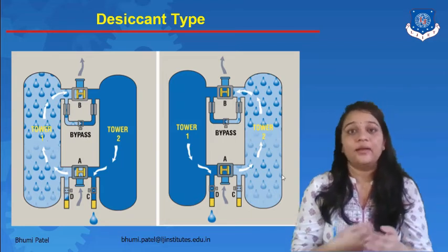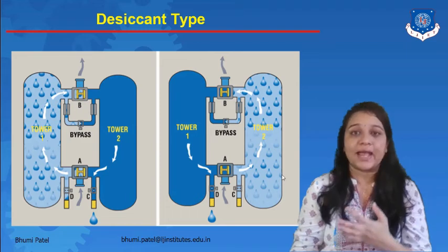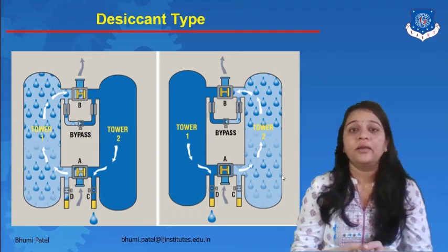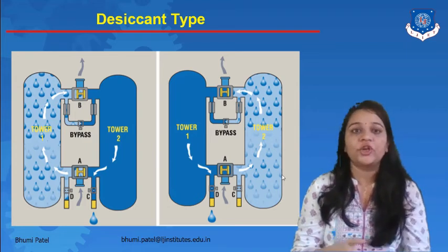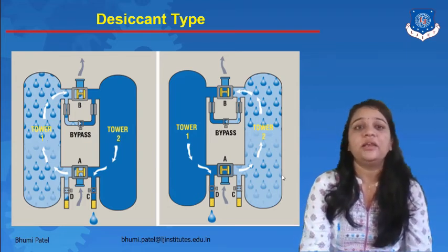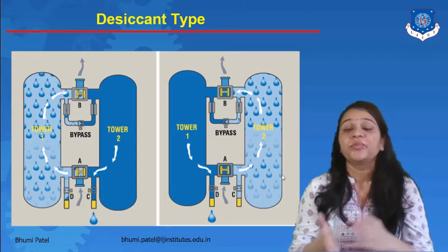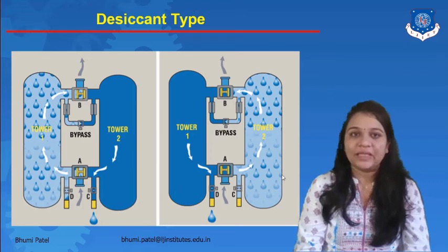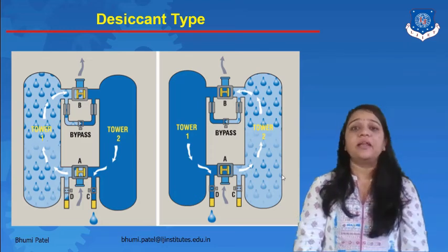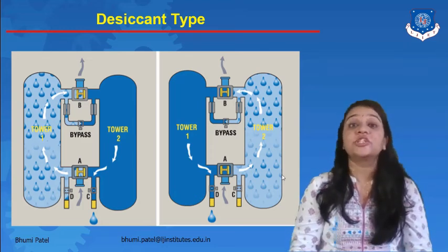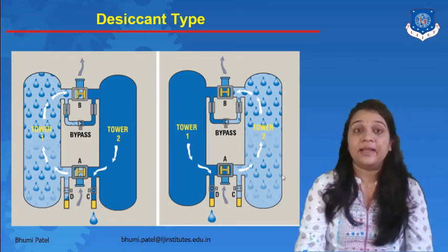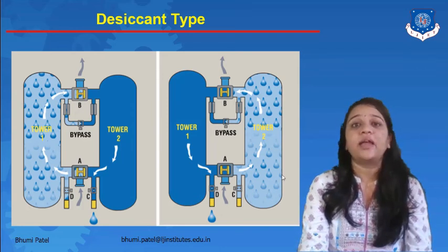Now when the moist air comes in contact with the desiccant, an equilibrium condition is established in which the relative humidity of the air determines the degree of saturation of the desiccant particles. Generally, the greater the relative humidity, the more moisture is absorbed, up to the 45% limit. Desiccant type dryers are filled with a solid desiccant such as activated alumina or silica gel, which removes the water vapor as the air passes through the desiccant bed.